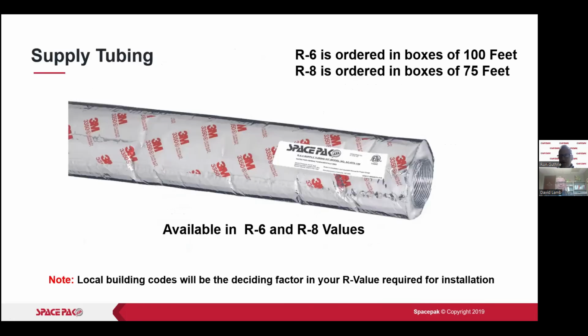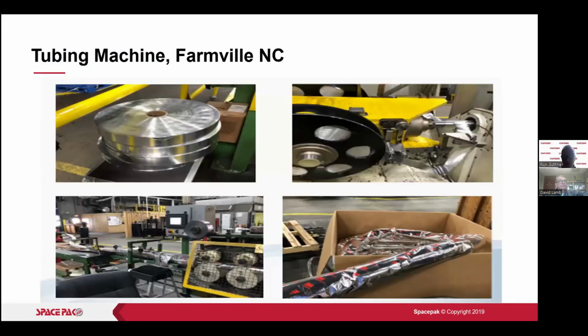So we have R6 or R8 as far as the R value. As far as we're concerned, R6 is fine, but if you're outside of the envelope, your inspector might want you to put R8 in there. R6 is certainly easier to get down through a wall, and again, it's only 2-inch, so there's not a lot of surface area where you have a loss. But we make R8 because some inspectors are going to require you to use that.